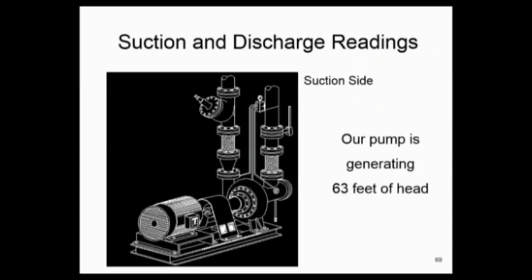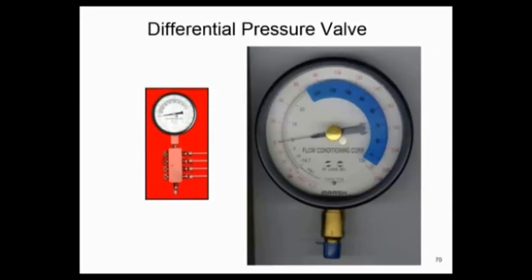If I got a fixed impeller size, which I already bought my pump, that's what I showed you a little while ago, what would my flow rate be? First of all, we would recommend to you use some kind of a common gauge, so you can get differential pressure with one gauge.